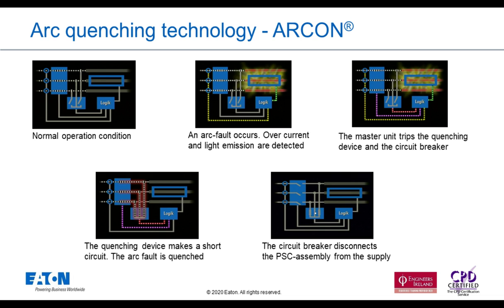We've also recently tested to the new IEC technical specification 63107, which ensures that the arc mitigation equipment installed into the assembly works correctly and avoids nuisance tripping, maybe due to switching operations or light signals that optical sensors can potentially pick up. The ARCON device has the current sensing equipment as well, so it uses both technologies, current sensing and light detection, before it initiates any arc quenching during the activation of an arc.